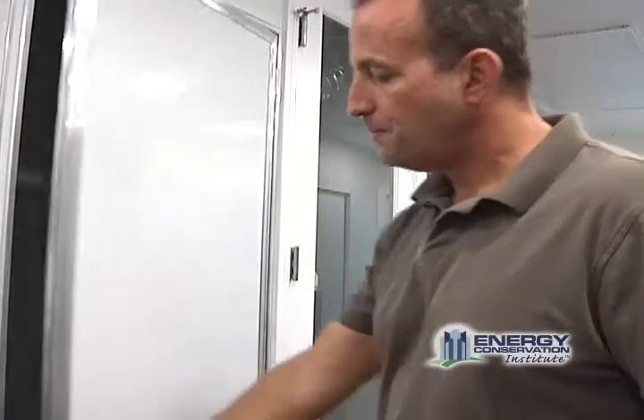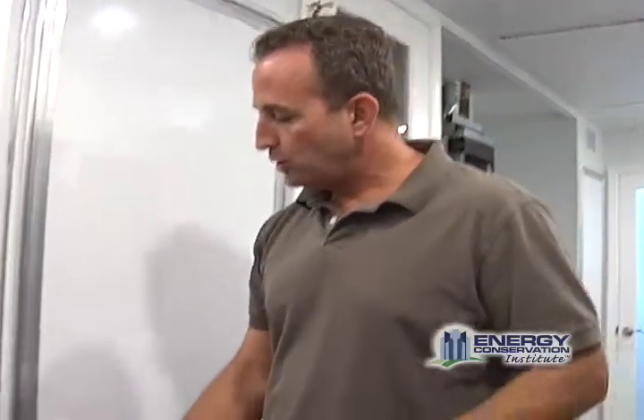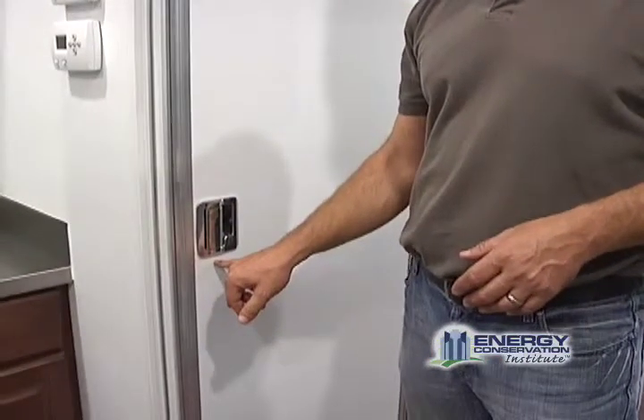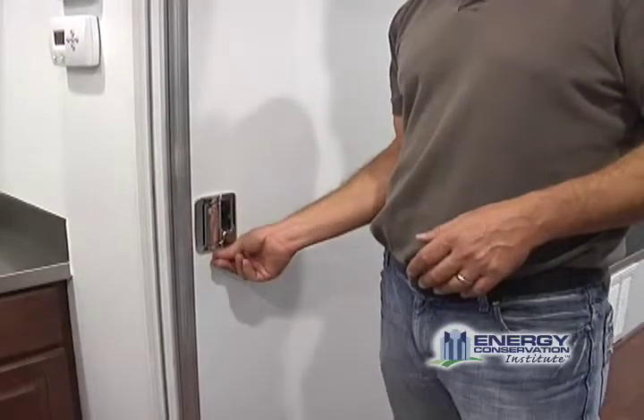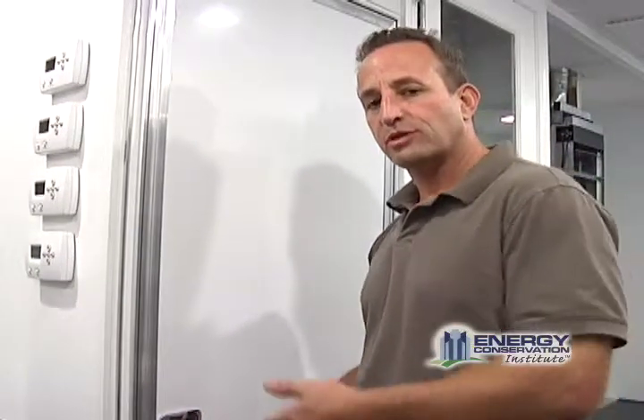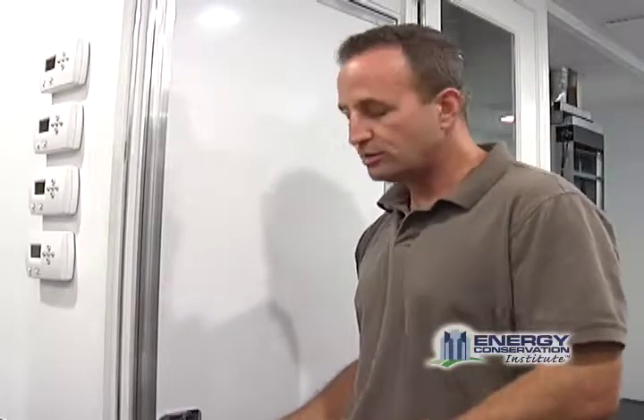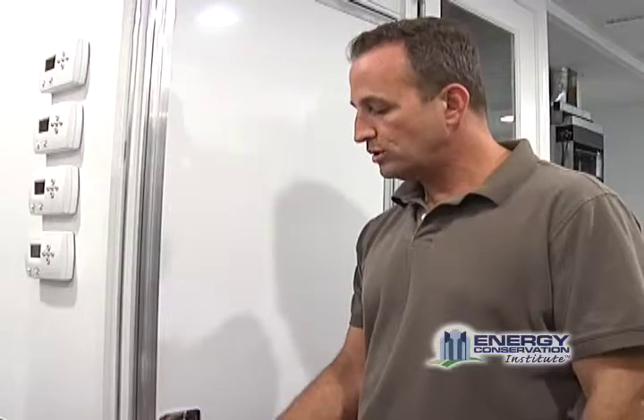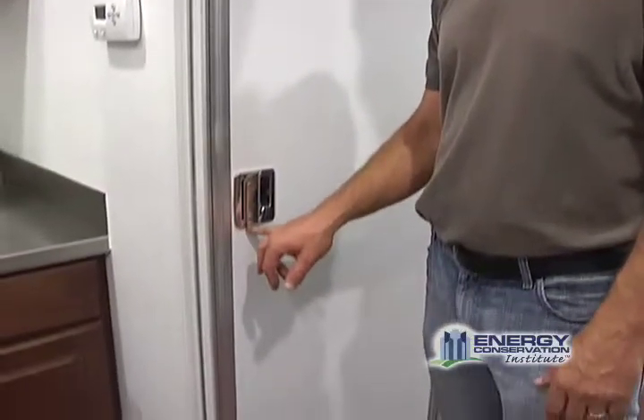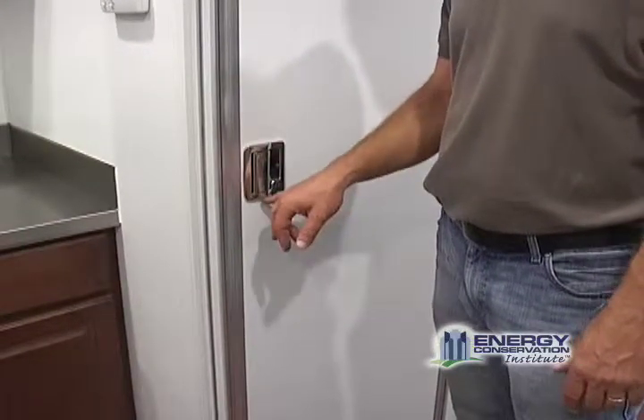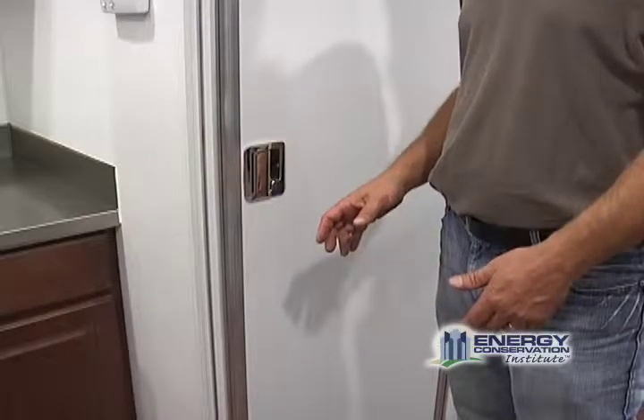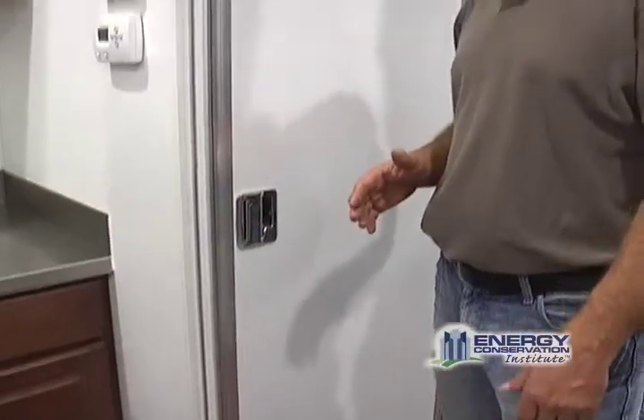The last thing I'll point out in this pressure test room is typically we'll drill a hole right here beneath the lock where we install a manometer tube. And we recommend that you do this so that you can easily test the pressure from inside that space to out here. Since there's nowhere to stick a probe through these doors, they're rather sealed. So just drill a small hole, stick a manometer tube all the way through, and then you're able to easily test the pressure across the space.